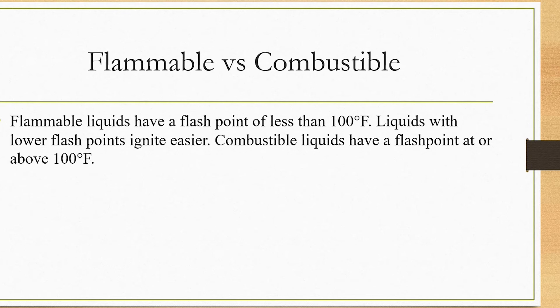Flammable liquid has a flash point of less than 100 degrees Fahrenheit; liquids with lower flash points ignite more easily. Combustible liquid has a flash point at or above 100 degrees Fahrenheit. This shows the limit between flammable and combustible liquids: flammable liquid has a flash point less than 100°F, and liquids with lower flash points ignite more easily, while combustible liquid has a flash point at or above 100°F.